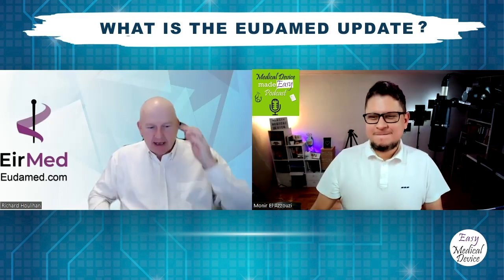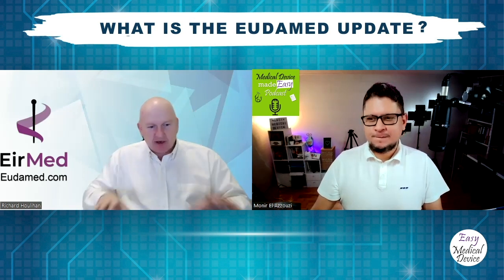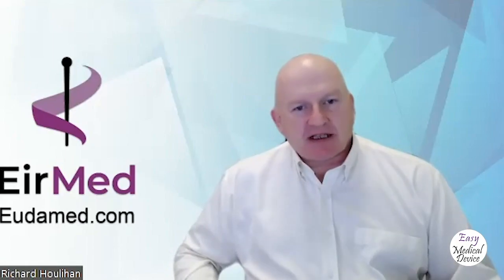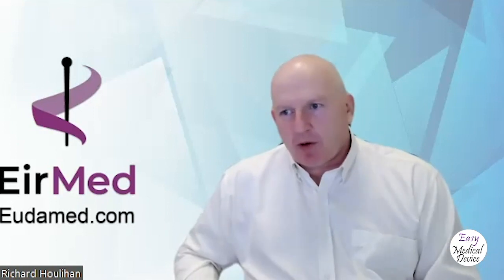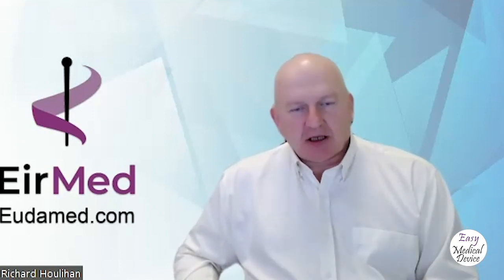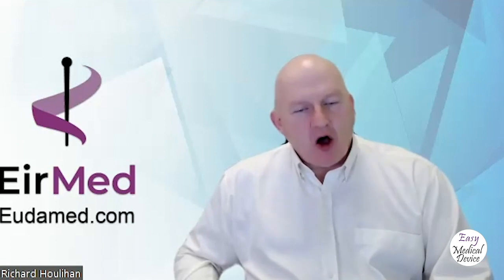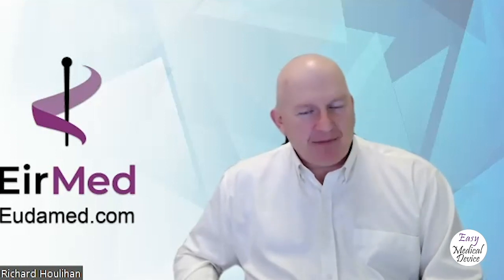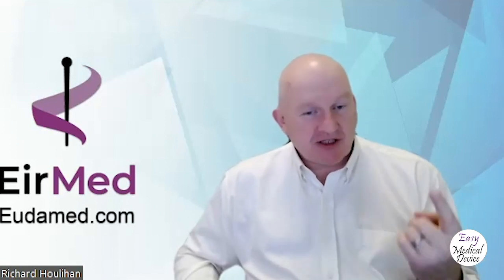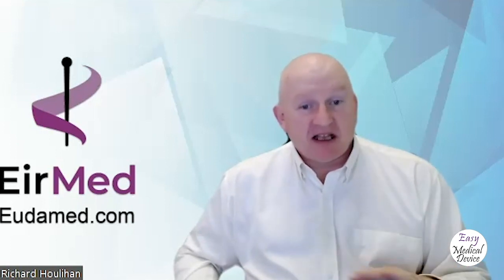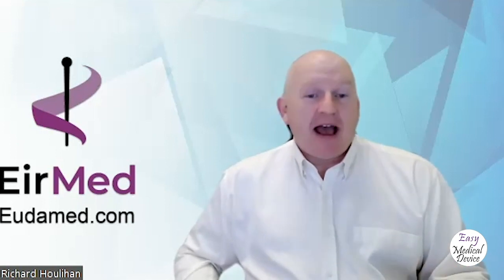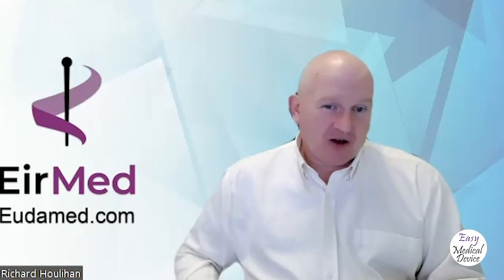One additional thing, warning, whatever way you want to put it. When EUDAMED was first conceived, or not first conceived, but when we were working on it, and on the initial information from the Commission, all the markets were not mandatory. Yeah. Initially, you just had to put in your first market, and you were done. They've changed it quietly.